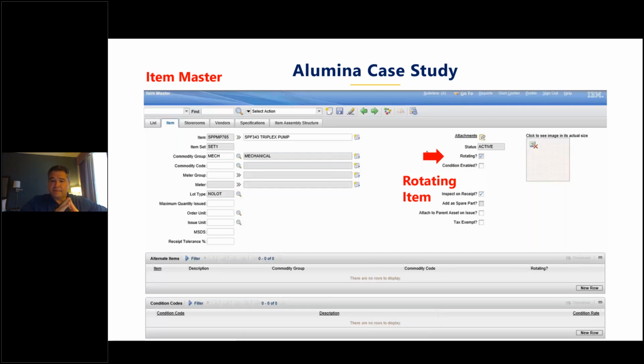why that's important. But ultimately, not being able to see that mechanical seal through its complete life, you're missing the connection that pump number 3 could be a bad actor, and you're having short mechanical seal life in pump number 3 as compared to say pump number 1. If we ran 5 years in pump 1, 3 years in pump 3, those are things that can highlight not only is it a location issue, but is it actually a seal issue? Is the seal that's being rebuilt no longer within tolerances?